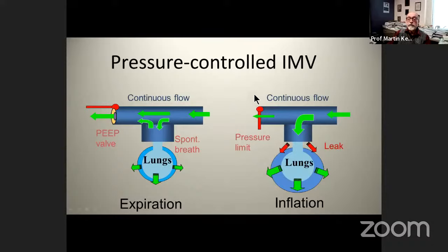And when the ventilator cycles on, the circuit is pressurized and gas enters the patient's lungs in proportion to the pressure within the circuit and the compliance of the lungs. And we're not worried about leak around the endotracheal tube because there's plenty of fresh gas available to maintain that set pressure, with excess gas overflowing over the pressure limiting valve. So this is all good. This is easy. We all know how to do this. It doesn't matter that there is a large leak, which is good.